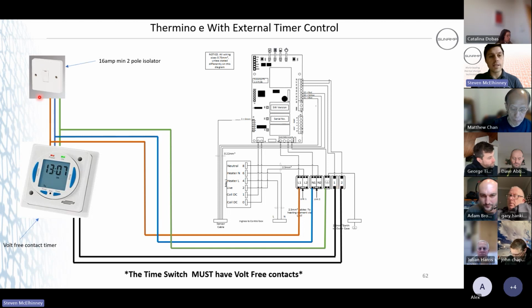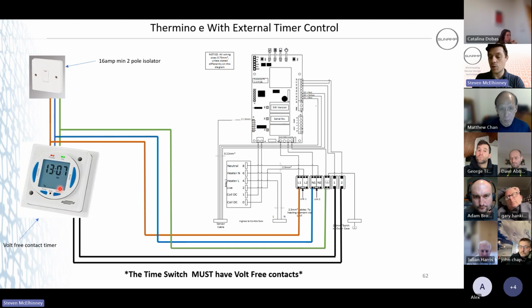So you've got a 16 amp 2-pole isolator here, feeding our permanent supply. You can piggyback off that if you need to power the motor in the timer, as long as the contacts are volt-free. I can't emphasize that enough. But the timer is really the master. So even if we generate a demand here, it's going to be the timer that's going to dictate whether the element comes on or goes off, because we're completing that control circuit for the element.